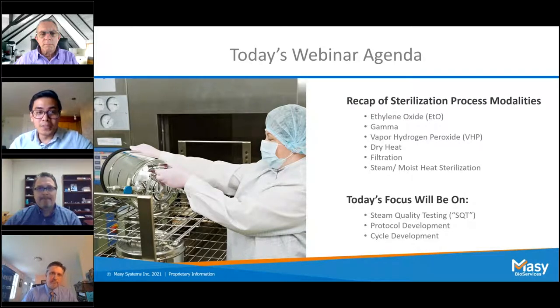Next we get into gamma sterilization, which is performed by exposing the product to a radiation source. These gamma rays can penetrate the product and deactivate any microorganisms that there may be. Next, we go to vapor hydrogen peroxide sterilization, which, very similarly to ethylene oxide, is used for medical devices, and it uses a high vacuum, low temperature vapor process to sterilize types of medical devices. We get into dry heat sterilization, which works with dry air. It's mainly used to destroy pyrogens and is used to sterilize items that may otherwise be damaged by moisture, which we see in steam or autoclave sterilization.